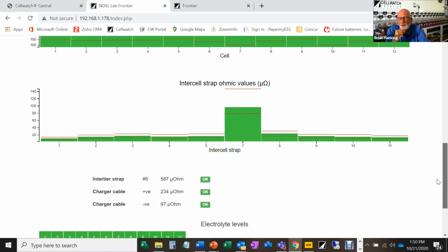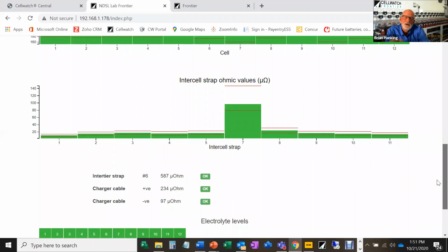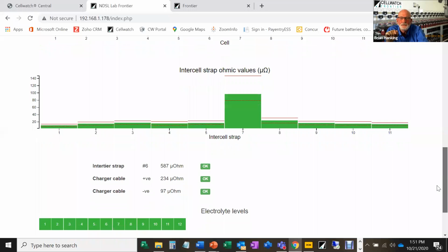We have a bigger system called CELLWATCH, which is primarily for UPS systems where there's a high volume of batteries and therefore a high volume of hardware. The difference is Frontier looks at dispersed, perhaps smaller batteries, while CELLWATCH looks at the same number or more batteries, but usually in one or two rooms. So it's a slightly different application.